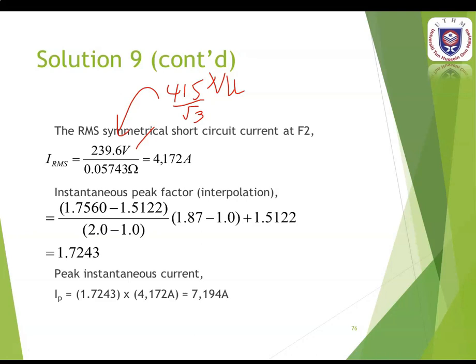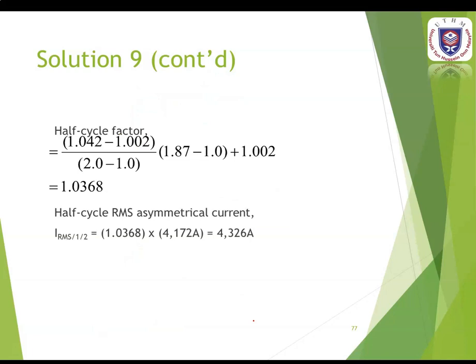To get the peak instantaneous current at F2, use the instantaneous peak factor from the asymmetrical table with interpolation, then multiply by IRMS. For the half-cycle factor, refer to the same table at the half-cycle factor column. Using the same procedure of interpolation and multiplying by IRMS, you get the half-cycle RMS asymmetrical current of 4326 amperes.